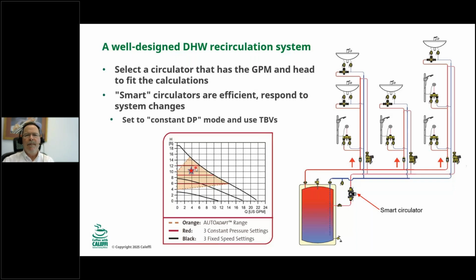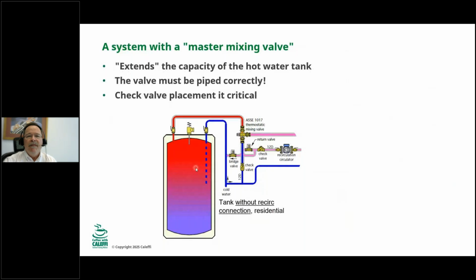Let's talk about master mixing valves. In general, a mixing valve will extend the capacity of a hot water tank. So that's why you would put that on the hot water tank at your house, to extend your 40-gallon tank, maybe extend that up to effectively a 50 or 60-gallon tank by tempering the water that goes out to your fixtures.